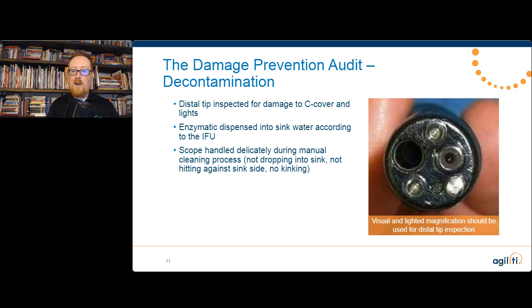Not only is that a waste of money, but enzymatic also gets very difficult to rinse off once you have too much, because it gets too concentrated. So it's very sticky. It makes it hard to rinse off. It leaves these residues behind. Let's give you a pro tip right now. If you go into your department and you look at your scopes, and you see any scopes where the numbers on the insertion tube are changing to a yellow or brownish color, that means there's enzymatic residue that is getting stuck onto your scopes regularly. And in addition to the fact that it's sticky and hard to rinse off, that means those are areas where the high-level disinfectant may not be able to make direct contact with the scope itself, because there's a layer of enzymatic residue stuck on there. So the high-level disinfectant hits that enzymatic and it just stops there. It doesn't make it through to the actual scope. And so it does create this inhibition. It inhibits the activity of the high-level disinfectant if we aren't dispensing correctly.